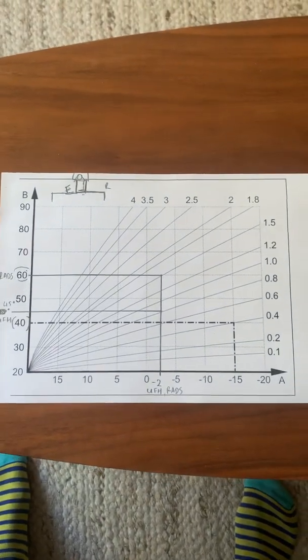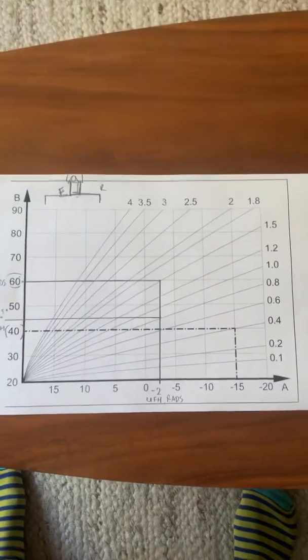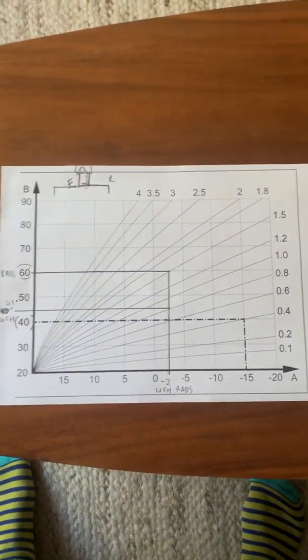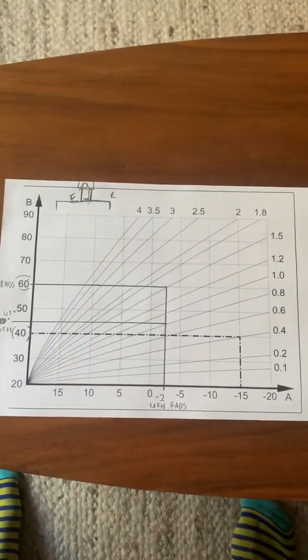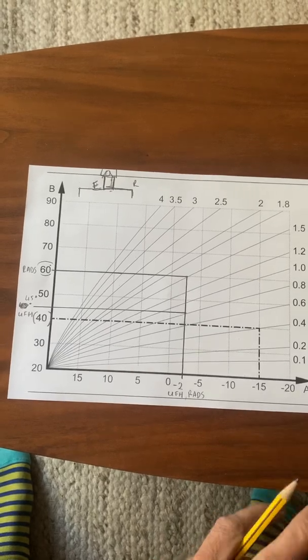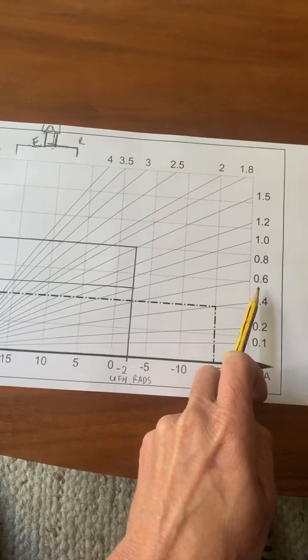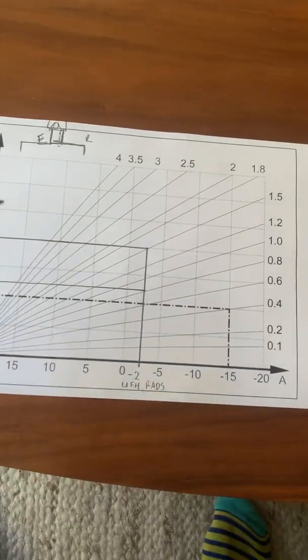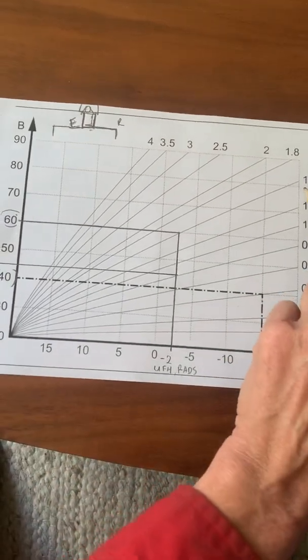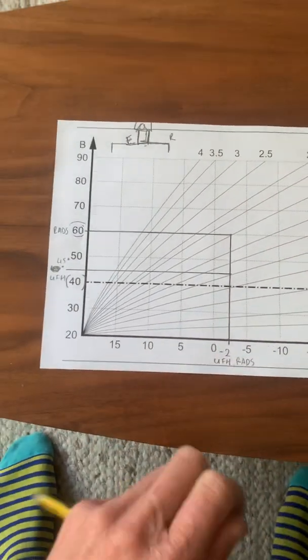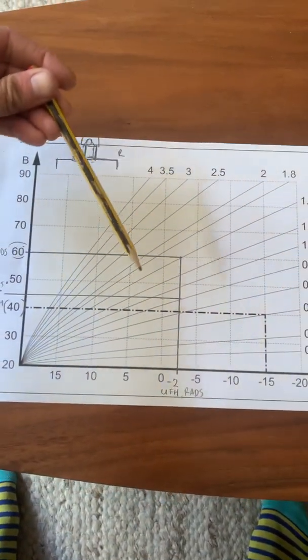This is a graph showing the curves you can select with the Vaillant for weather compensation. I selected 0.6 for the underfloor heating and then I selected 1.5 for the radiators, and that's the curve the boiler will follow.